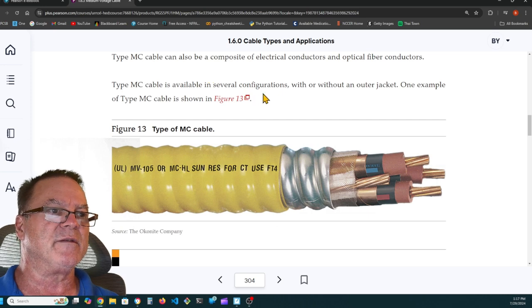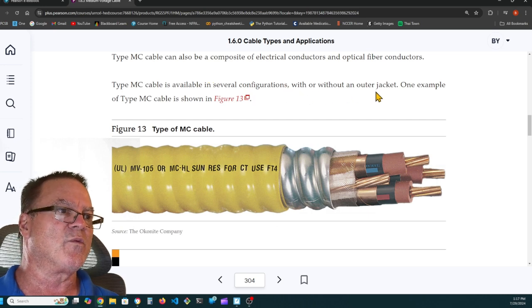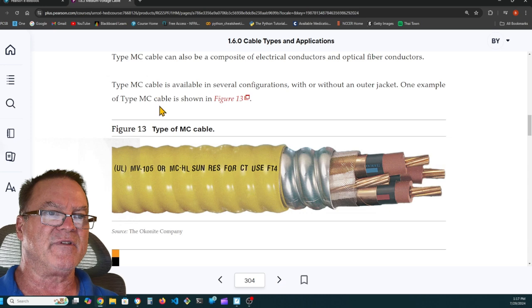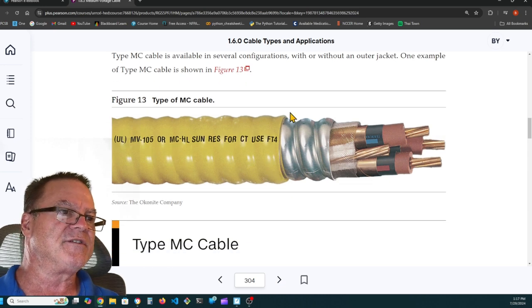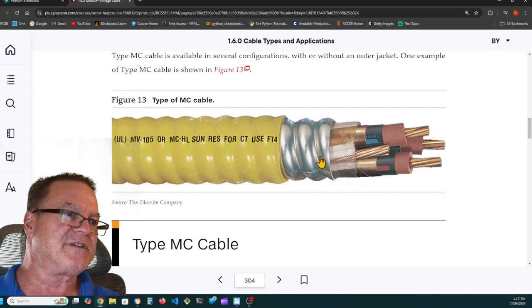Type MC cable is available in several configurations with or without an outer jacket. One example of type MC cable is shown in Figure 13. So it has this aluminum spiral wrap or corrugated extruded outer sheath, and that protects the conductors inside. And then if it's going to be outdoors, they'll also put this plastic thermoset covering over the whole thing, and that protects it from moisture.